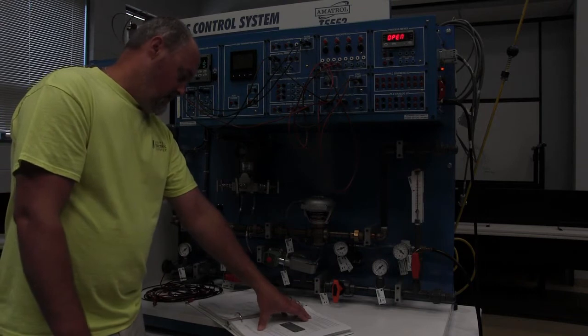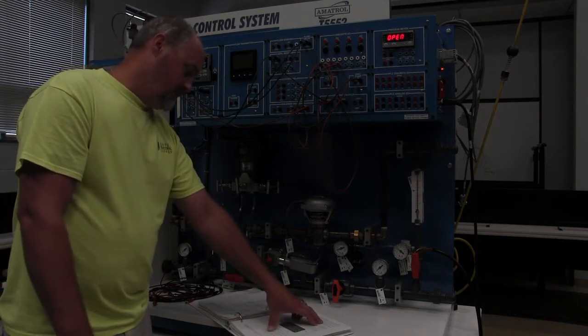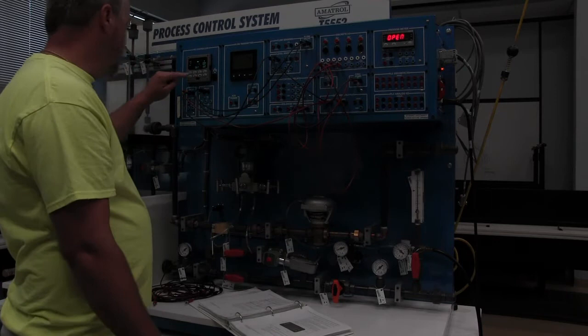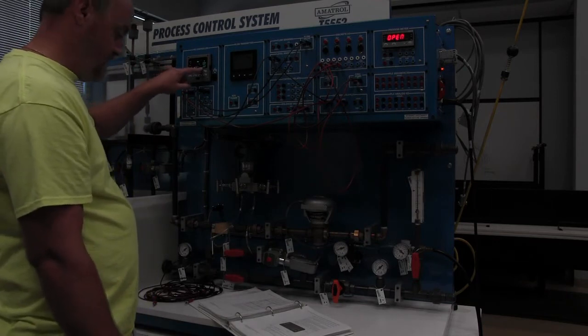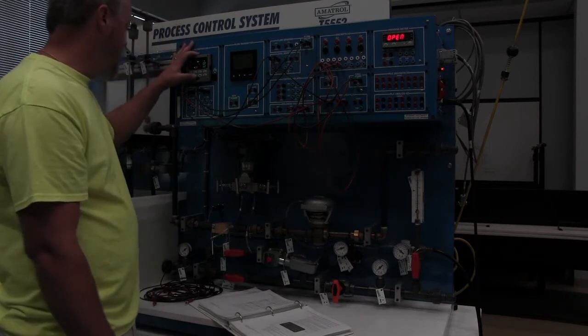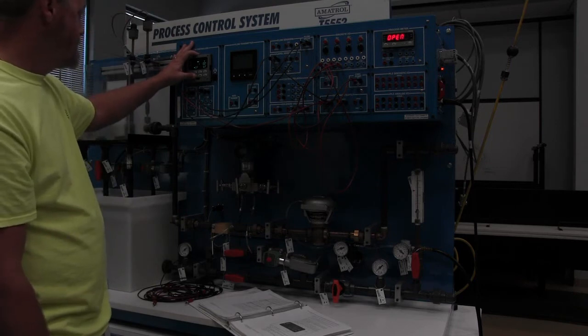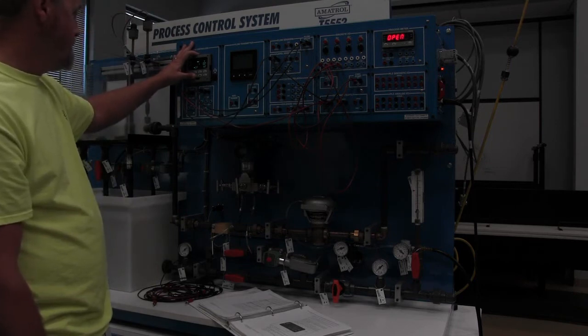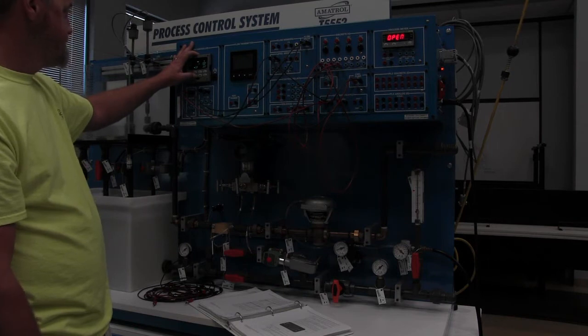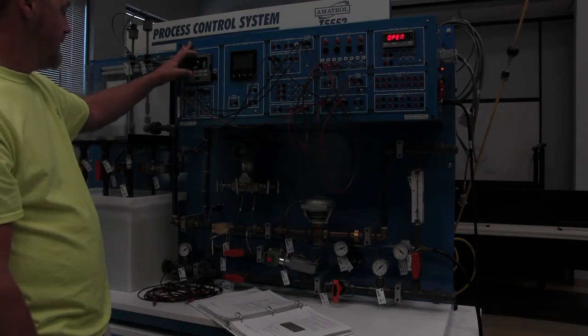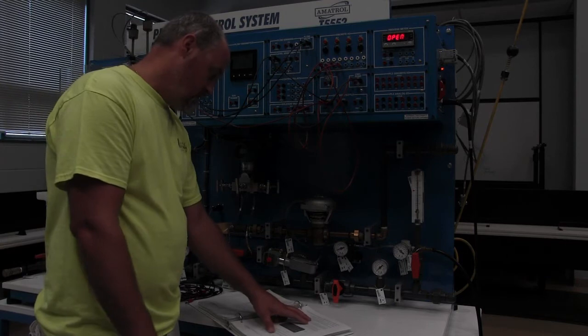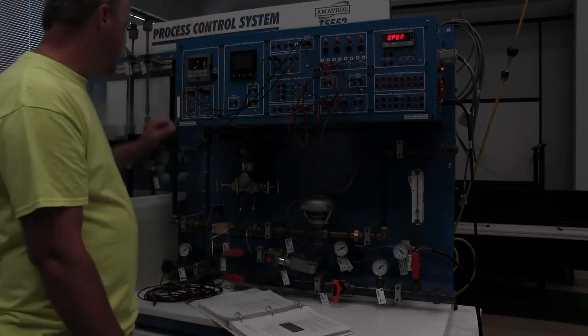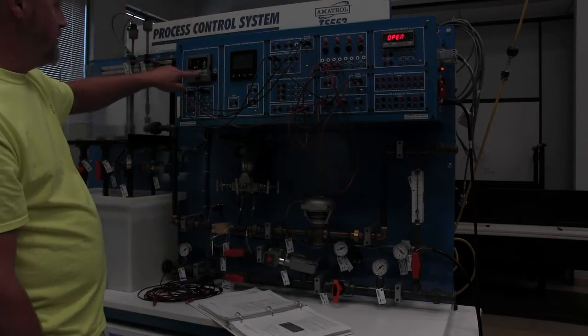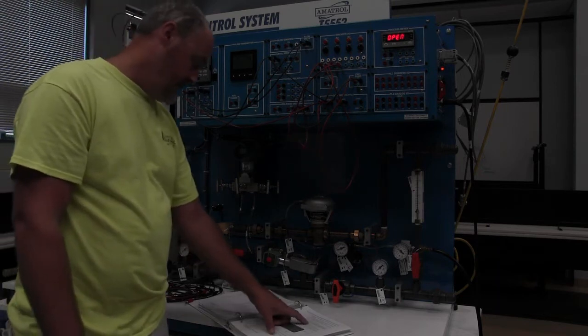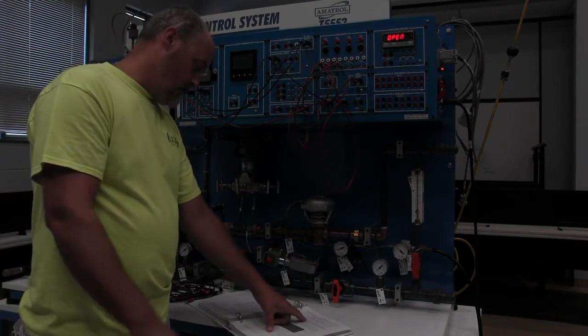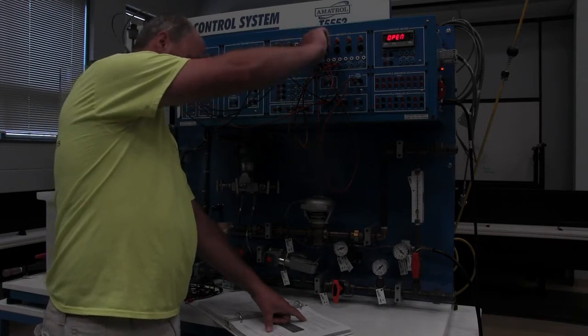Alright, use the lower display key, the set point value in the lower display. So set point is 0. We want to make the set point a value of 3.0. Alright, so we have a value of 3.0. Place the controller in automatic mode. Right now it's manual. We're going to push the manual auto button for an A for auto. Turn selector switch 1 in the on position.